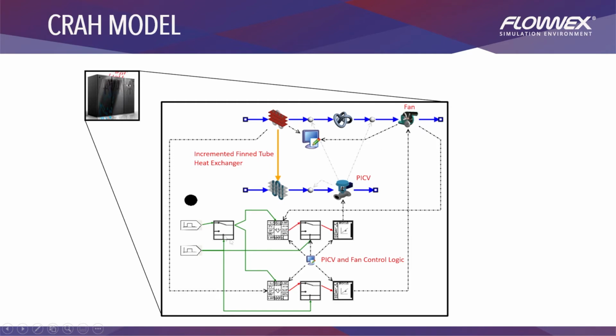The rest of the control that you see around here is some digital control for us to use when simulating the trip of a CRA. Here we might look at what happens to the PICV during trip, if it maybe fully opens or fully closes. And it's possible to change this behavior to investigate what is going to be best for the individual configuration of these CRAs to get the best performance in a thermal ride-through event.